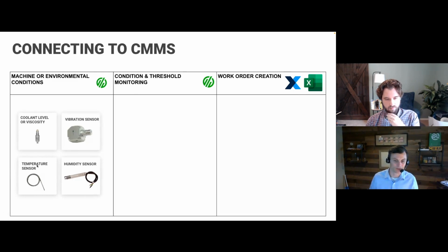A really cool example of that is a customer that does paint and has paint lines, and they have to abide by a certain standard so the particulates in the air are not violating the local EPA. By taking sensors before and after the filter, manufacturers can recognize when that filter is going bad.